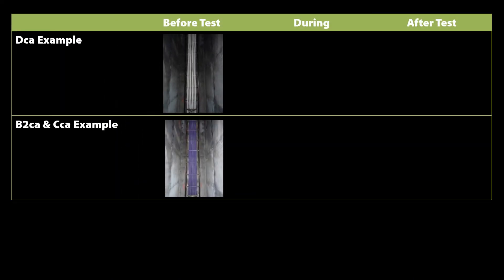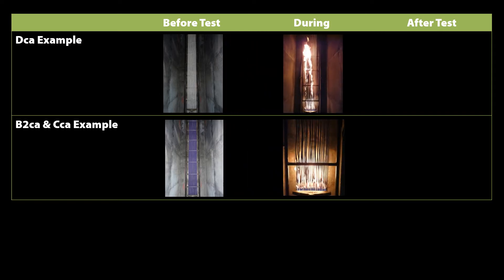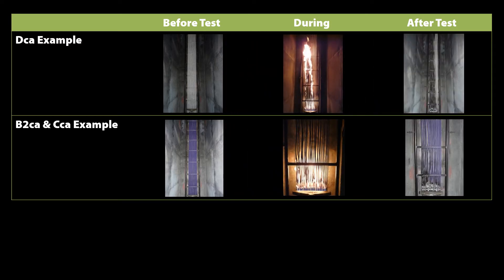The duration of the EN 50399 test used to classify smoke production is 20 minutes, during which time a 20.5 kilowatt flame is applied to the test sample. Typically this involves 24 individual cables that are attached to a ladder in a vertical test chamber.